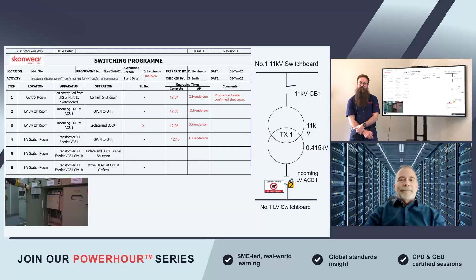Same switch room, transformer T1 feeder, VCB circuit, isolate and lock busbar shutters. So this is withdrawable switchgear. It might be different if it's fixed pattern. Different switchgear is going to obviously denote what you do on your switching program. That isolate process might be multiple steps. As you'll see here, it's not as straightforward to isolate it. So as we said before, isolation is that disconnection with a suitable air gap to prevent re-energization. In this instance, it's a full withdrawal of the circuit breaker.